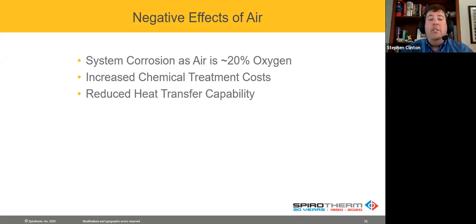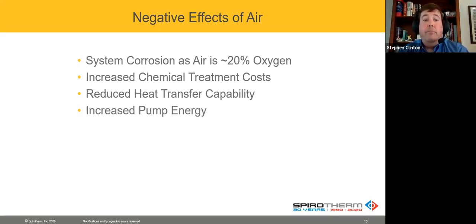Well, think about it. What does that fluid touch? Let's say you're in a chilled water system. It affects the chiller, the coils, heat exchangers, affects everything in the entire system. Same thing for a heating hot water system. Those in the different parts of the country that are familiar with glycol will probably get this immediately, because if I were to come to you and say, I'm taking a water system and turning it into a glycol system, you more than likely would just go time out. Don't do that, because you just derated every piece of equipment in the system. That's really what air is doing as well.